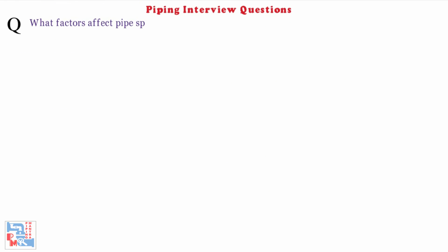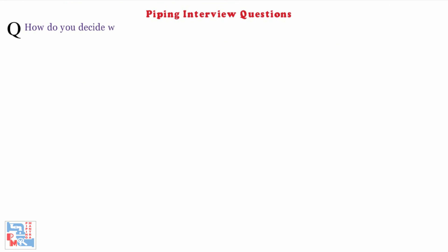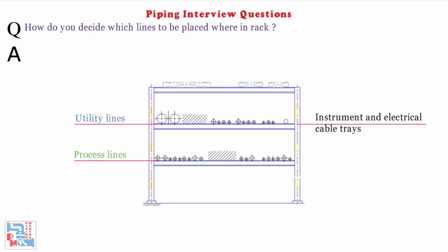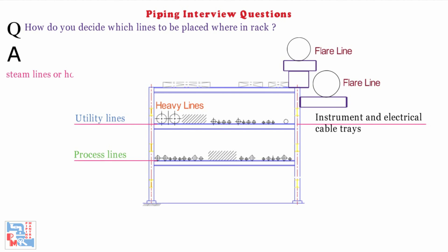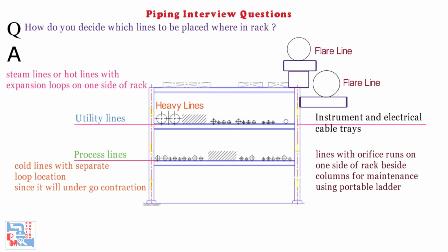Next: What factors affect the pipe span? Factors affecting pipe span are size, schedule (i.e., thickness of pipe), liquid or vapor, and insulated or bare pipe. Next: How do you decide which lines to be placed where in a rack? Process lines on lower level, utility lines on top level, instrument and electrical cable trays on utility level or separate topmost level, heavy lines near column, flare lines outside the rack on cantilever beams or inside rack above top level, steam lines or hot lines with expansion loop on one side of rack, besides column for maintenance using portable ladder. If we have cold lines and hot lines running on same rack, we have to plan their loop locations separately as hot lines will have expansion and cold lines undergo contraction.